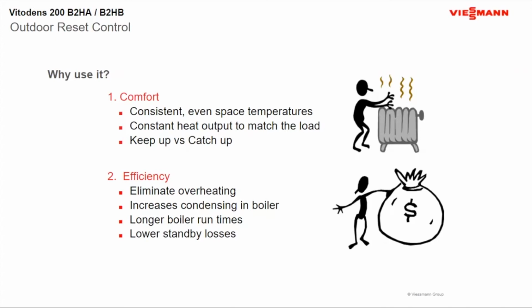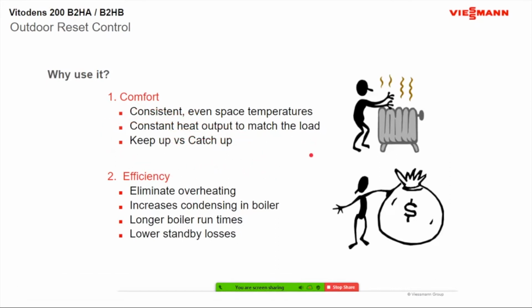So it's important to do a heat loss calculation. And what I found in these areas was there were way too many emitters in the house. A lot of times there was one room that was way overheated, and by the time the temperature got to the last room, there was no more temperature. So it's important to do a heat loss when you're doing this type of thing. And to me, it's more important to keep up than catch up. You get those calls, hey, my house is not heating up all the way now. Well, how many emitters do you have in the house, or are your emitters blocked?